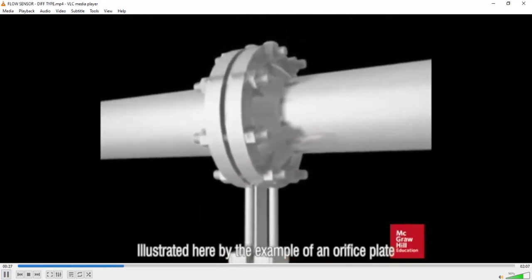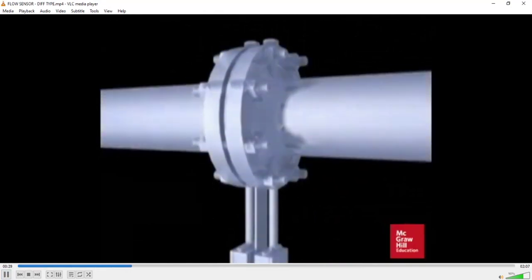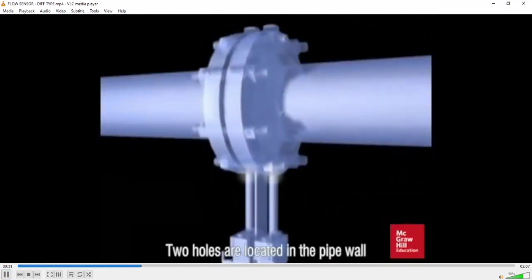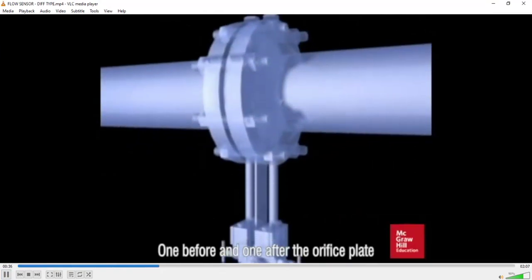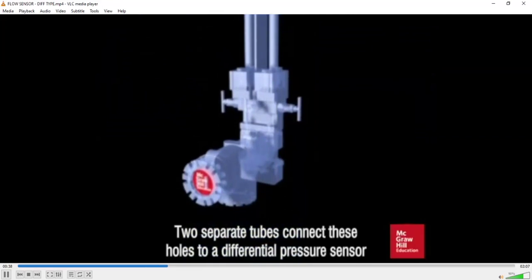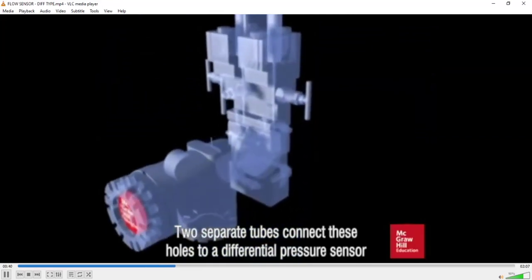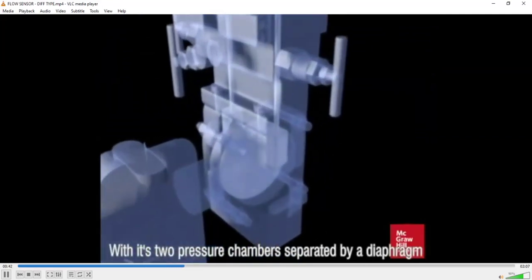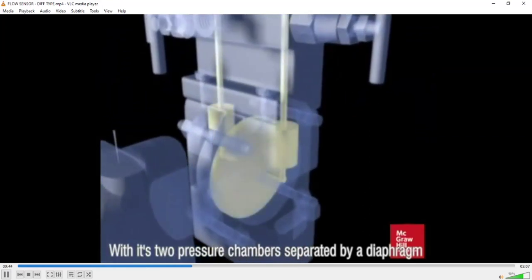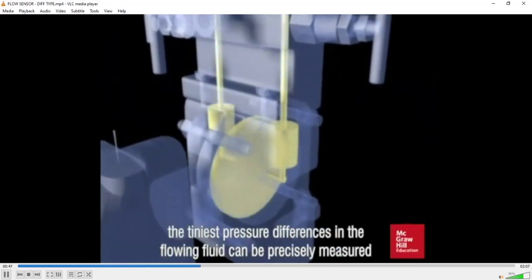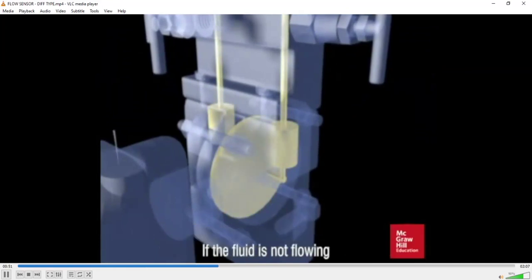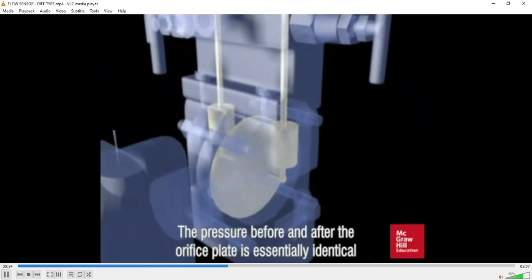Illustrated here by the example of an orifice plate. Two holes are located in the pipe wall, one before and one after the orifice plate. Two separate tubes connect these holes to a differential pressure sensor with its two pressure chambers separated by a diaphragm. The tiniest pressure differences in the flowing fluid can be precisely measured. If the fluid is not flowing, the pressure before and after the orifice plate is essentially identical.